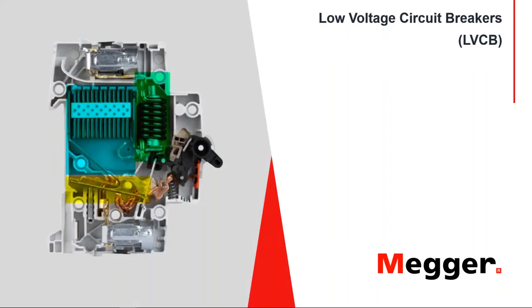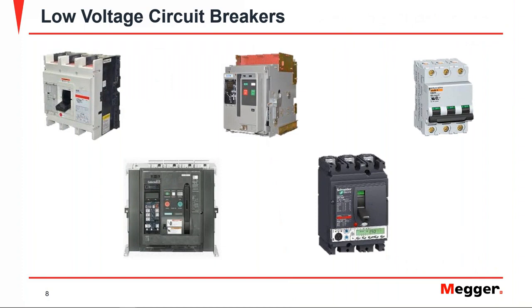So, starting with low voltage circuit breakers, answering the very basic question of what a circuit breaker is: we can say that it's a mechanical switching device capable of making, carrying, and breaking currents under normal circuit conditions, but most importantly, also breaking currents under specified abnormal circuit conditions such as those of short circuit. It will be the only switching device in the power grid capable of breaking those currents under those abnormal conditions. Therefore, circuit breakers are indispensable switching devices in the power system.